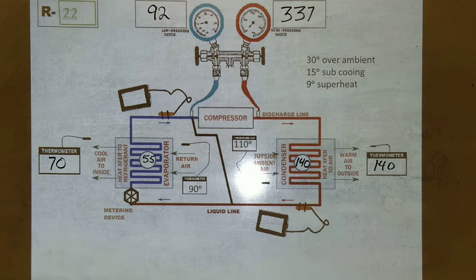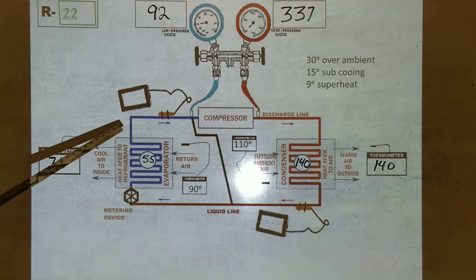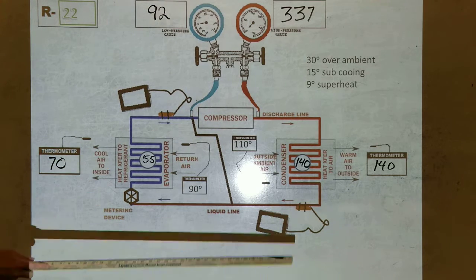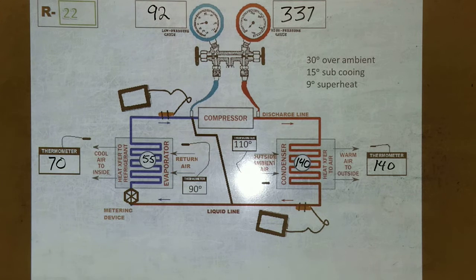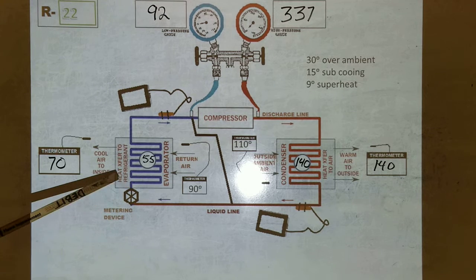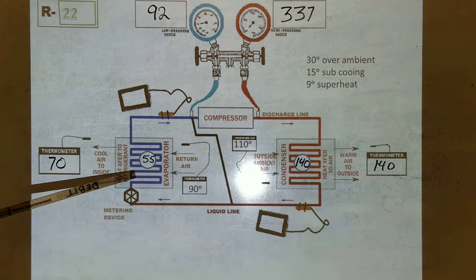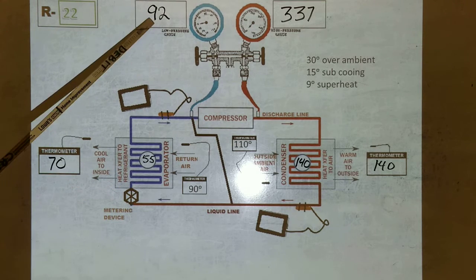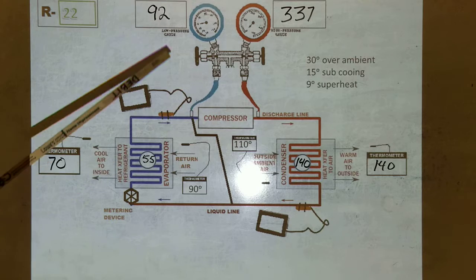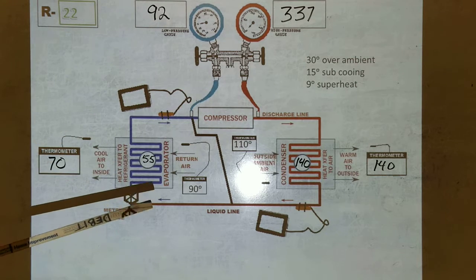The couple other readings we're gonna take here are what they call the suction line temperature and the liquid line temperature, and that's gonna give us our superheat, or we're gonna determine our superheat. Now let me tell you a little bit about superheat. Superheat is the temperature above the evaporator saturation temperature. The superheat is above that. Okay? By how much?